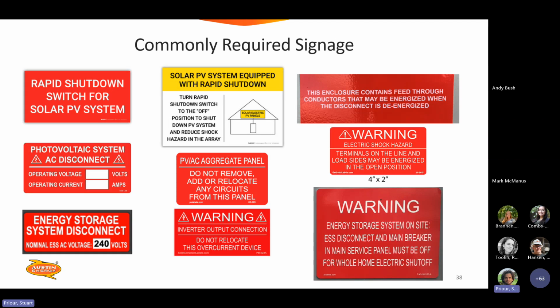So here's some common labels that we require. They're generally ones that the NEC requires. There is one that is kind of unique to us, which is that top right one. This enclosure contains feed-through conductors that may be energized when the disconnect is de-energized.